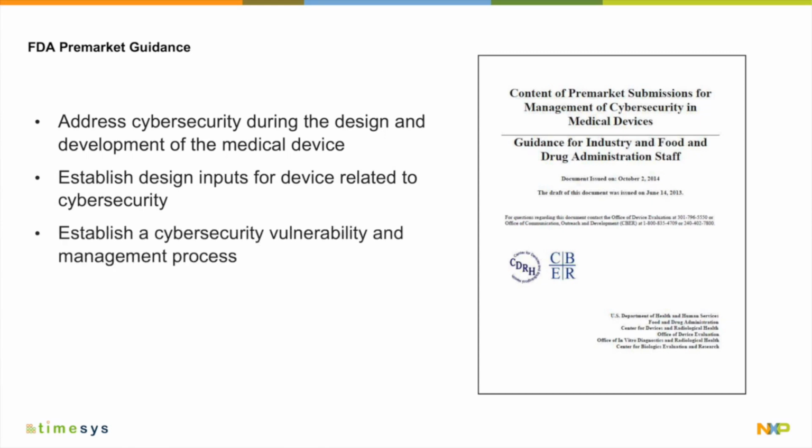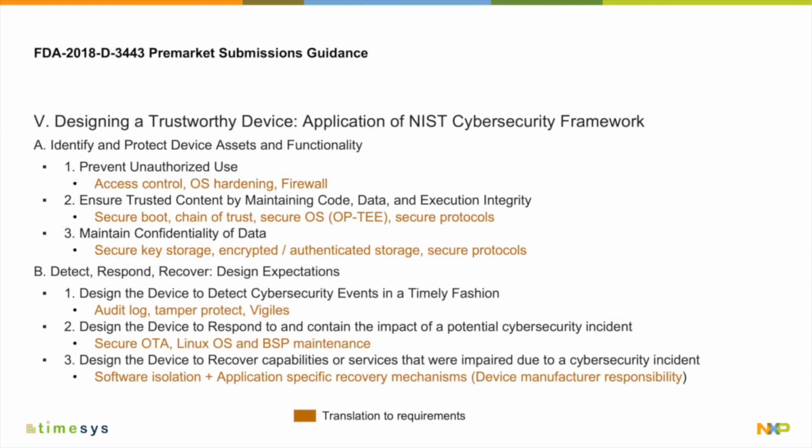Cybersecurity is one of those areas that FDA now mandates is taken care of during the design and development of a medical device. It establishes design inputs for the device related to cybersecurity, and has requirements for the process to manage the vulnerabilities long term. In the next slide, you can see an excerpt from this pre-market submission guidance document. And this one is about designing a trustworthy device. You can see here different requirements and how those requirements translate into tasks that an engineering team typically needs to implement.